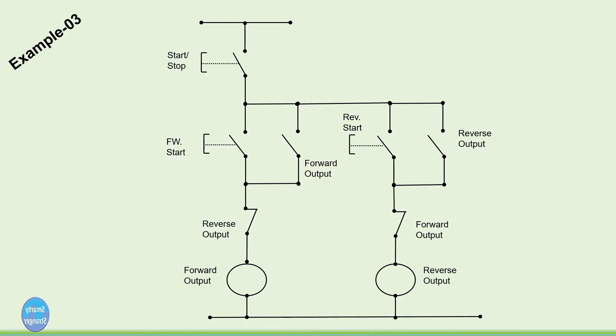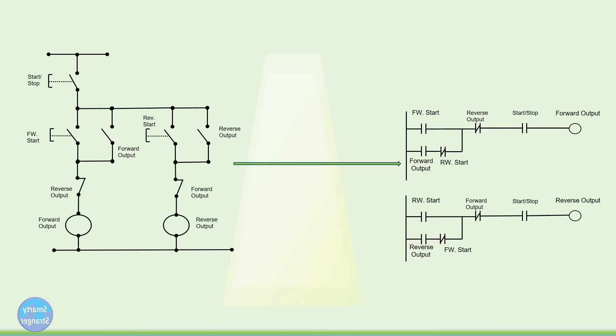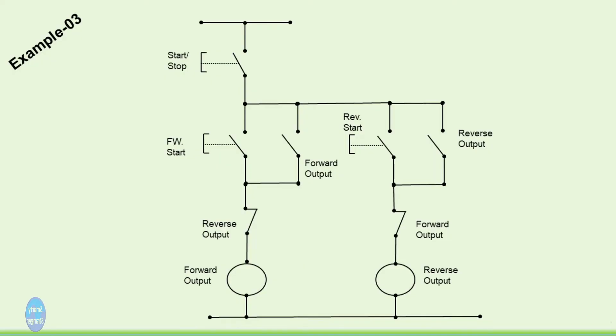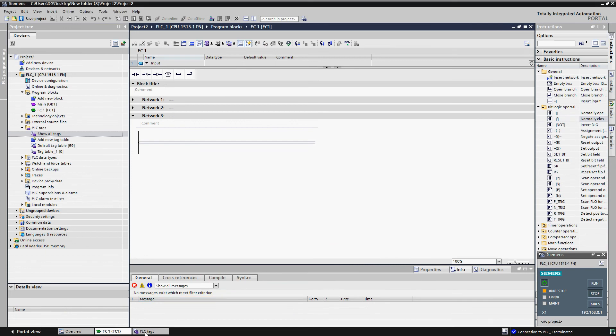Let's see another example which is more complex than the previous one. By remembering the basic symbols, you can convert any electrical diagram into a PLC program. Here we are using one switch for stopping the whole circuit, one switch for forward start of the motor, and one switch for reverse start. Two contacts are used to keep the motor running, two contacts are used to break the connection for opposite starting, and two outputs are used for forward and reverse start.